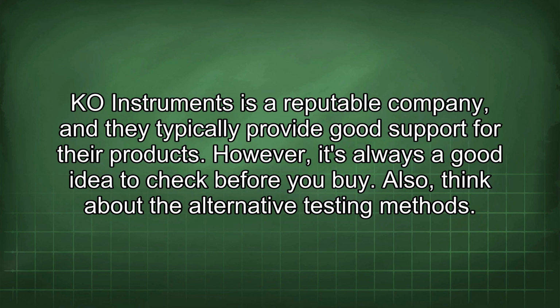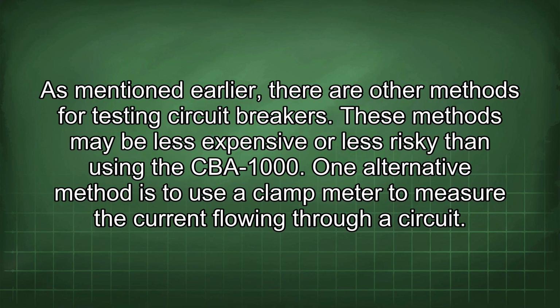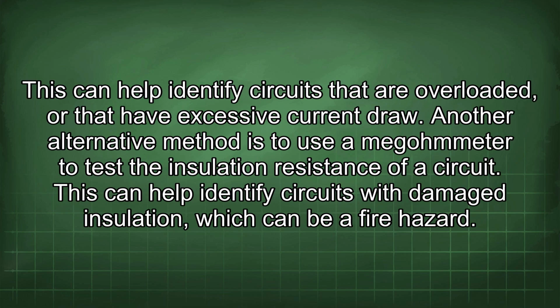Also, think about the alternative testing methods. As mentioned earlier, there are other methods for testing circuit breakers. These methods may be less expensive or less risky than using the CBA-1000. One alternative method is to use a clamp meter to measure the current flowing through a circuit. This can help identify circuits that are overloaded or that have excessive current draw.